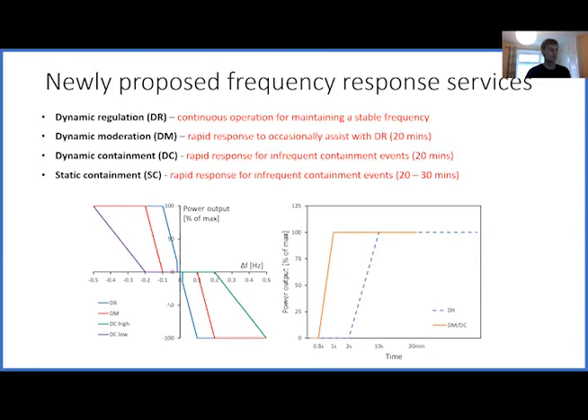Dynamic moderation and containment are much faster responding. They need to respond within 0.5 seconds and be at full required output by 1 second. And their profiles: moderation is between 0.1 and 0.2, and containment is whenever the frequency goes outside of 0.2 Hertz. And then there's also something called static containment, which is not proportional to frequency. It switches on when the frequency gets to a certain point. But I won't discuss that further in this presentation.